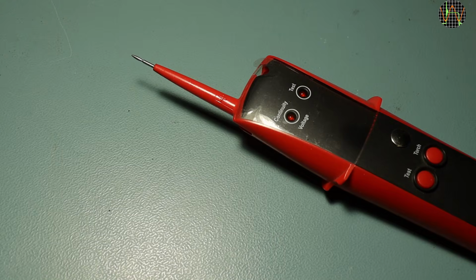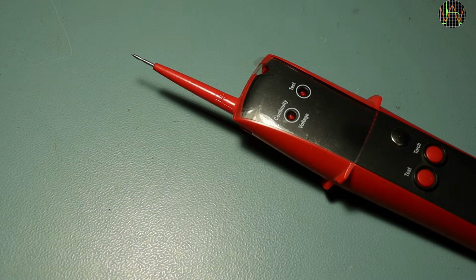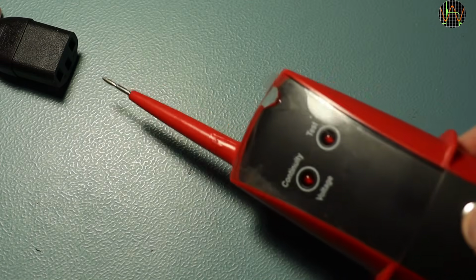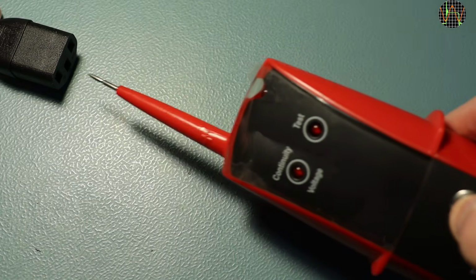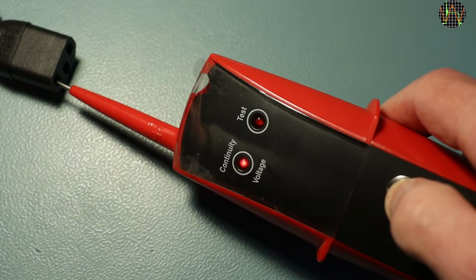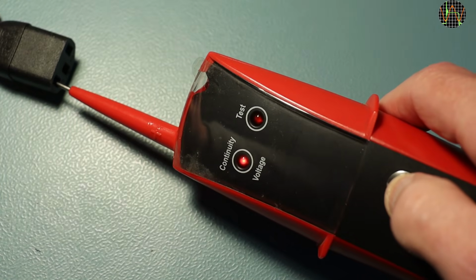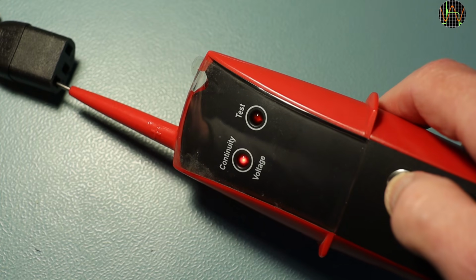This use of your hand as one part of a continuity probe is very fast and ideal when working away from a bench, like standing on a ladder. Using a touch of the round metal disc, you can check for the presence of a voltage between 60 and 250 volts. The tester buzzes if there is.